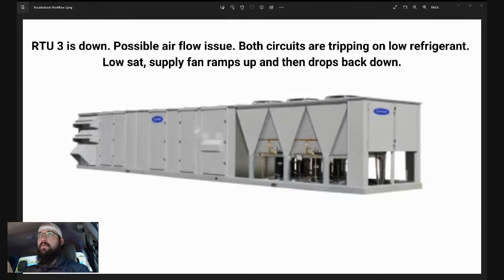So what I would encourage you to do is spend more time making sure that the overall mechanical is sound and good. So when I walk up to a system and I begin to do any kind of troubleshooting, or when I begin to try to evaluate, okay, what do I do next? One of the last things that I do is hook up gauges at all. If the interface itself has pressure readings I can use to evaluate, I may reference those to a certain extent, but I won't actually include those into my primary troubleshooting process until I'm confident in the rest of the system. More specifically, in this particular application, something weird was happening with the fan on this RTU.